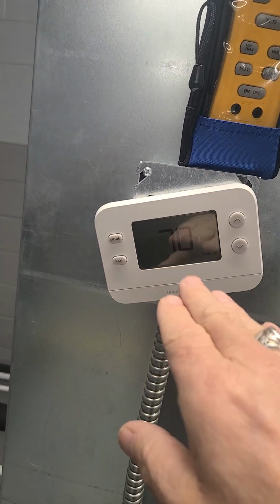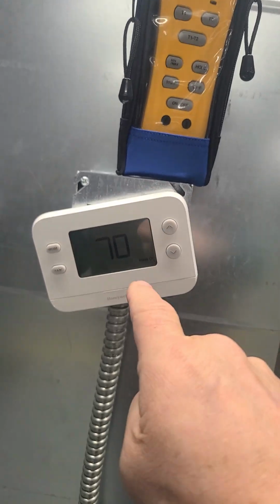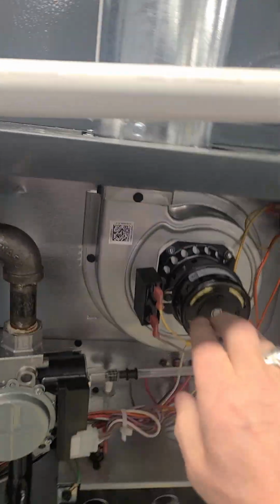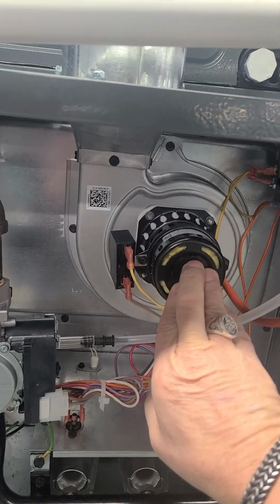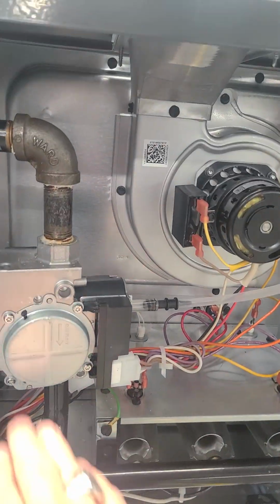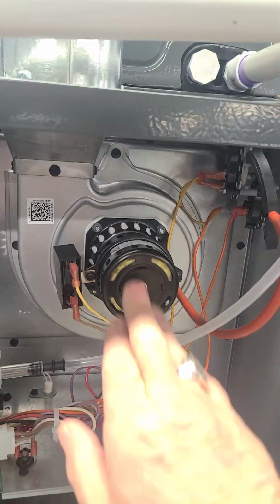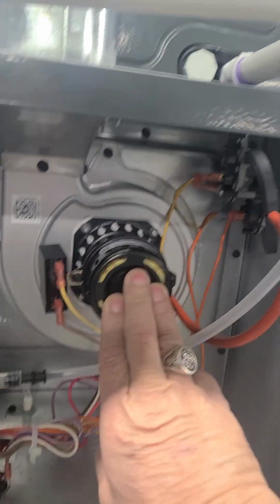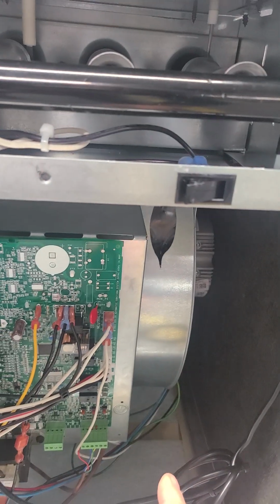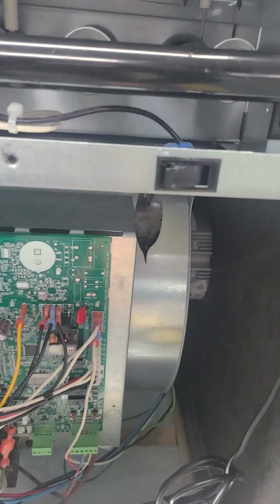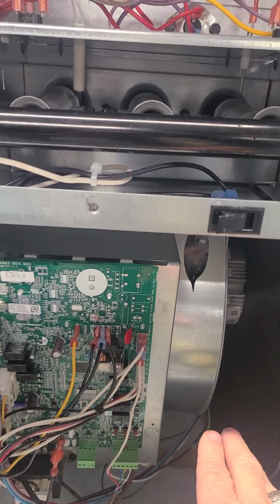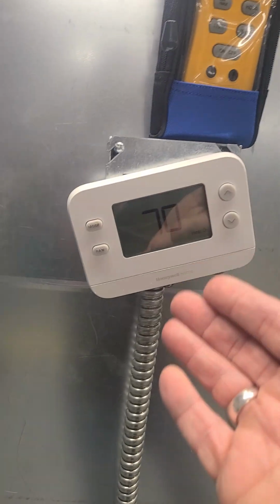So once the air is being blown into the conditioned space, heating up the conditioned space, and the thermostat hits that set point, it then opens the contacts in that W terminal back to the system board. The first thing that happens, the gas gets shut off, and then the flames stop in the burners, and the inducer motor runs for another 15-second purge. After that 15-second purge, the blower motor gets on a shutdown delay, also programmed. It'll be on high speed for the first 30 seconds and then low speed for the remainder of that shutdown. Once the blower motor shuts down, the heating cycle is complete, and the unit is waiting for its next call for heat.